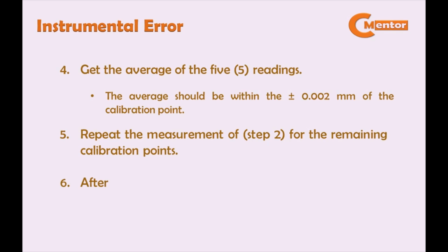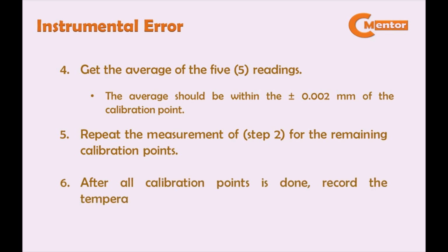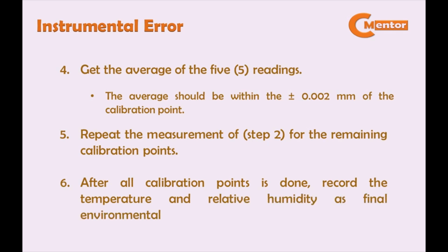And lastly, after all calibration points are done, record the temperature and the relative humidity as final environmental condition. Take note that the temperature difference of the final and initial environmental condition must not be more than 1 degree Celsius. Otherwise, the calibration process shall be repeated.